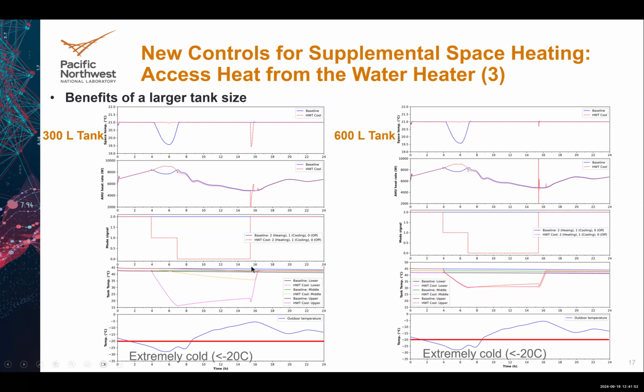When you switch back to heating, you can see the tank temperature will increase, right, to reach the tank temperature set point. However, you see the issue, right? When we switch back to heating, the space temperature cannot be maintained during a period of around half an hour. So that's why we further increase the tank size to see how a double size tank performs. We still keep the same discharge period, around 3 hours during the early morning. But you can see the space temperature can still be maintained at the set point, and we avoid the deep drop when we switch back to heating when the outdoor temperature is the hottest.